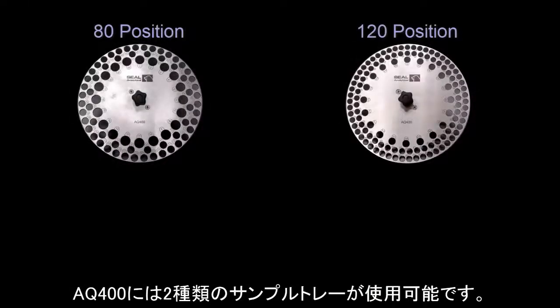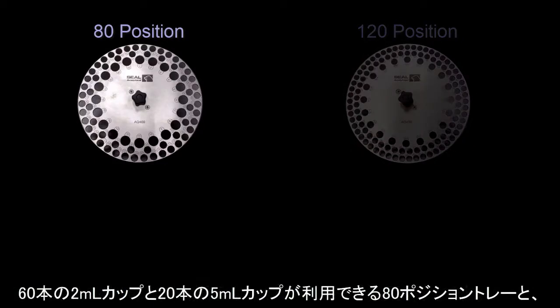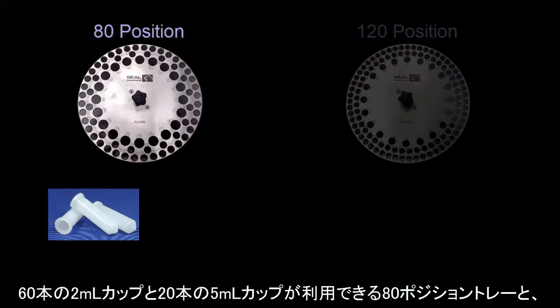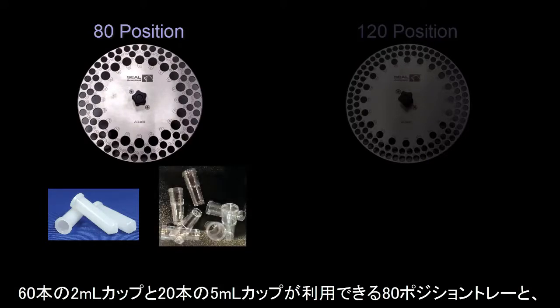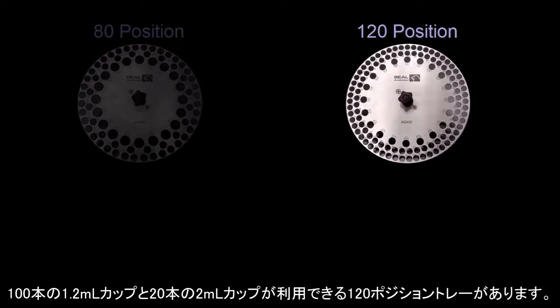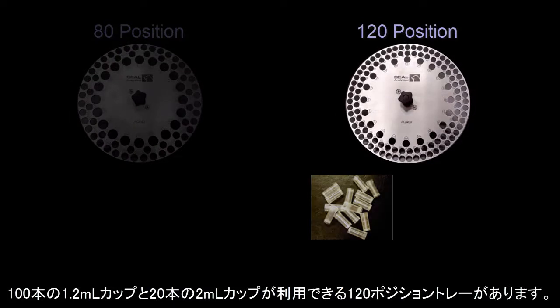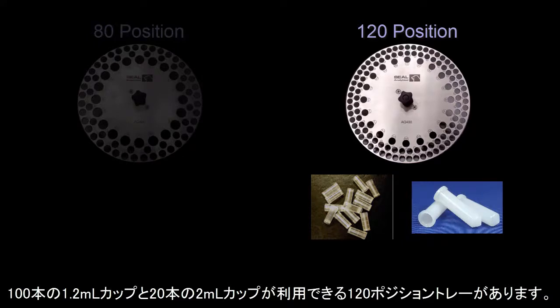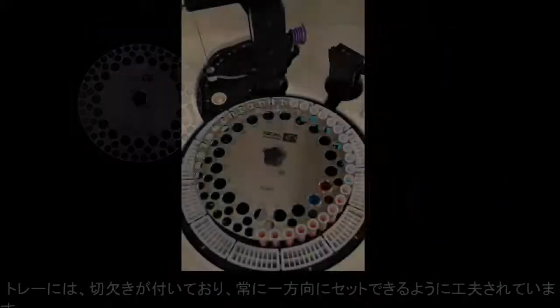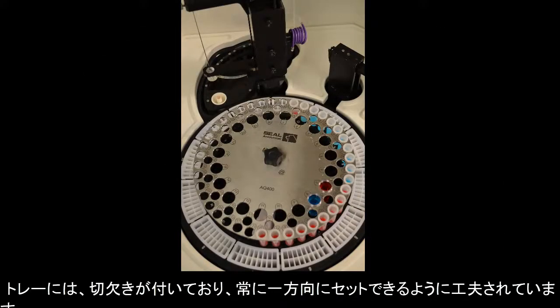The AQ400 has two possible sample tray configurations: an 80 position that holds 60 2-milliliter sample cups and 20 5-milliliter sample cups, and a 120 position that can hold 100 1.2 milliliter sample cups and 20 2-milliliter sample cups. The sample trays are keyed so that it only fits on the instrument one way, which guarantees that it is always aligned properly.